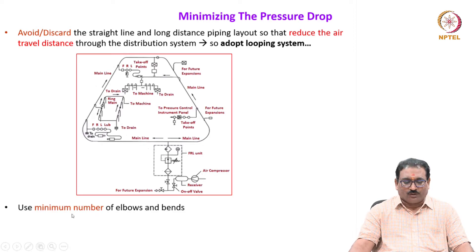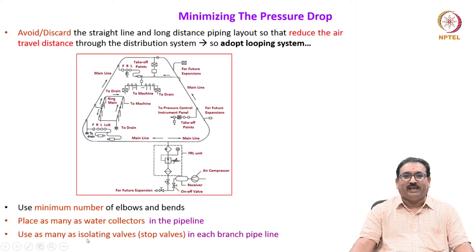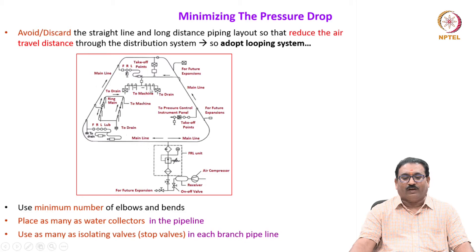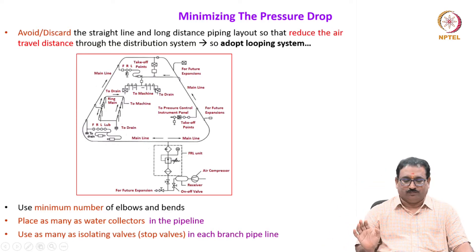Use the minimum number of elbows and bends. Place as many water collectors in the piping as possible. Use as many isolating valves — on-off valves, stop valves — on each branch, because this is very essential. If a branch is not working, the on-off valve cuts it off and air flows through the main line to the next branch. Open the on-off valve to the required branch only as and when required, otherwise keep it closed, because air losses in piping are significant.